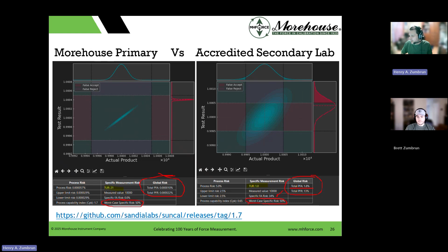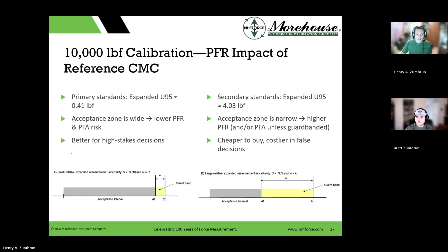So if we look at the impact, the easiest way to sum it up is I have that large acceptance interval. And if I have something that has severe consequences and I evaluate my likelihood - if it has severe consequences, it's on the risk decision. Even with likelihood, I'd probably search out the best standards to calibrate that device.